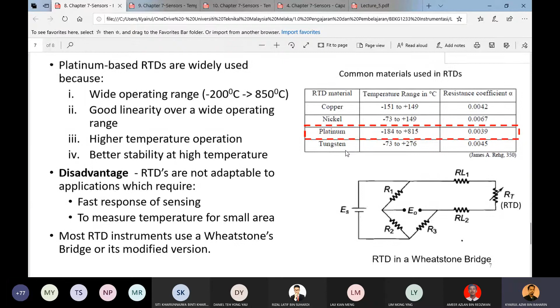But there are two main disadvantages. Number one, it has a time delay — when it senses, you don't get the result instantly. There's a slight time delay. This relates to the fast response of sensing. If you need to detect rapid temperature changes, like every second or every few seconds, RTD isn't suitable, because it takes some time to display the correct temperature.